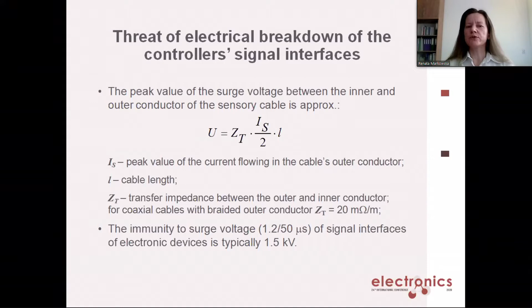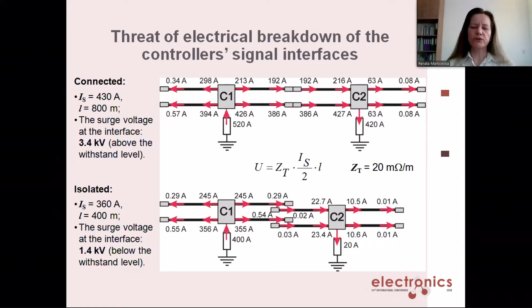It was shown that in the case of the connected configuration, the resultant peak value of the surge voltage of 3.4 kilovolt is likely to exceed the withstand level of the controller's interface. In the case of the isolated configuration, the resultant peak value of voltage, 1.4 kilovolt, may be regarded as below the withstand level of the controller's interface.